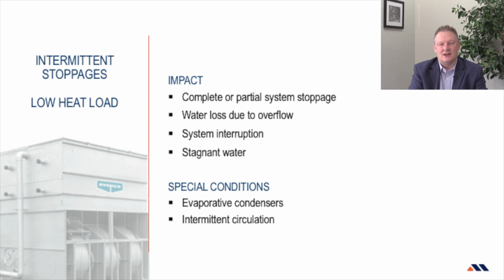These environments are very similar to the evaporative condensers as well, where their irregular operation will allow for the basin water to stagnate with no biocide treatment for days. When the system starts up again, sometimes with no warning, the complete system can become contaminated. No matter what the reason is for cooling water stoppage, maintaining the adequate water quality can be difficult.